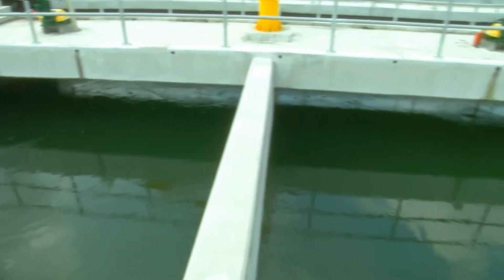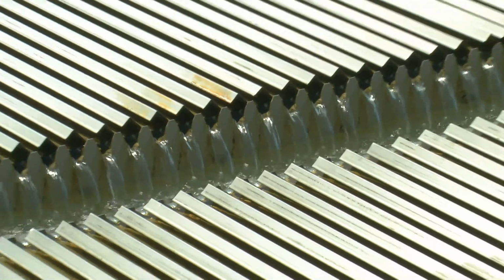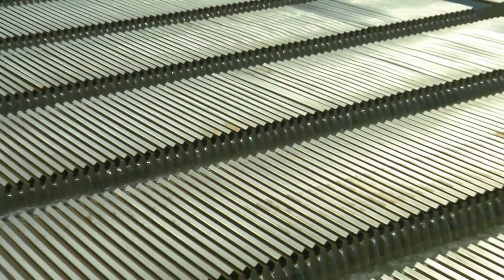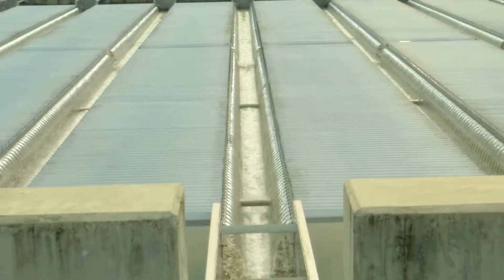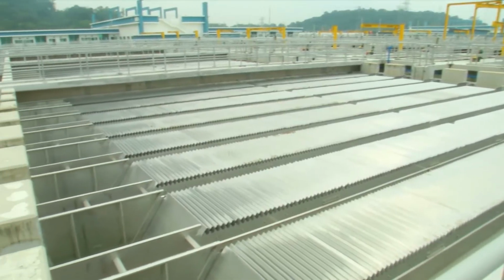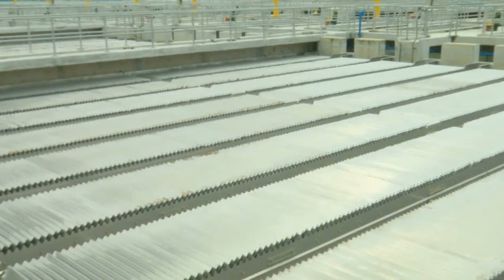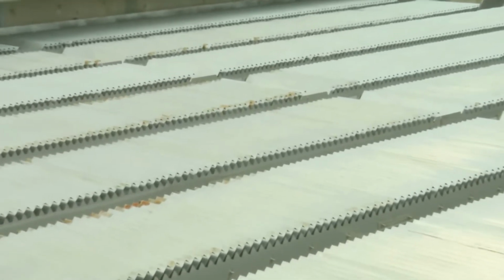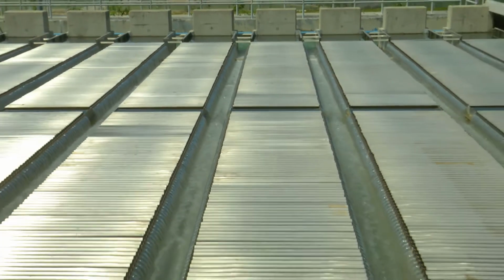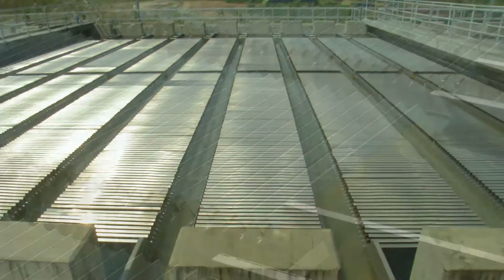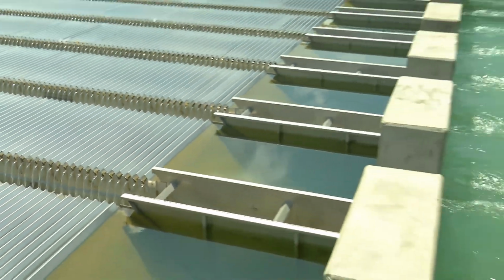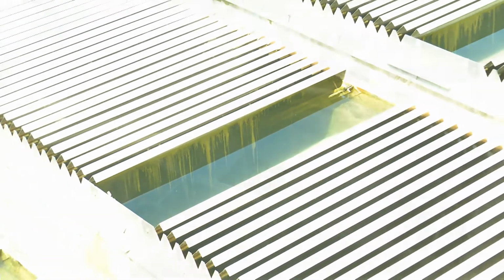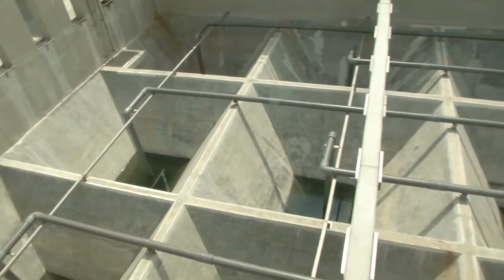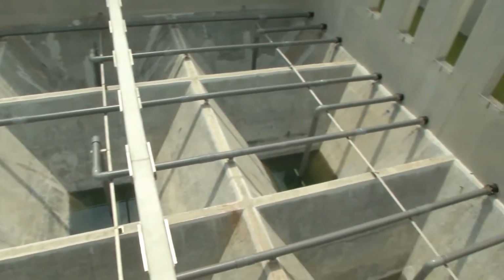Raw water from the flocculation tank is distributed evenly into each lamellar cell from the bottom of the channel. Outside, on the channel walls, lamellar plates are installed at an inclination of 55 degrees to the horizontal. The water flows upward between the lamellar plates. Clarified water is directed to the outlet channel. Solids which settle on the lamellar plate form a layer which slides down the plate and settles into the compartment underneath the lamellar plates.